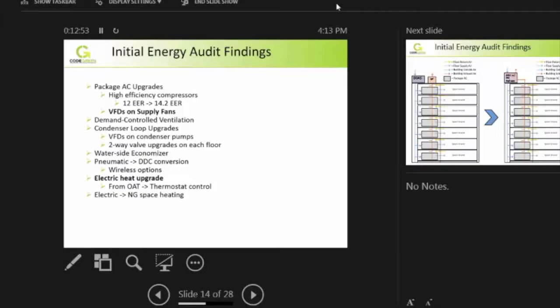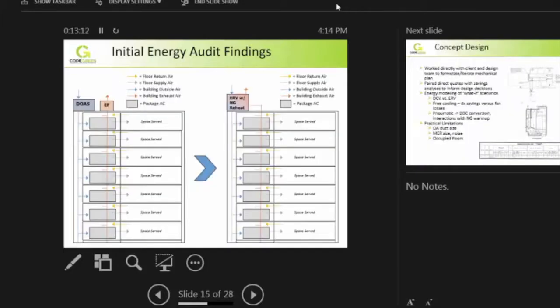Water-side economizer had actually been taken out of a lot of the existing package AC units in the building, so there was an aversion by the O&M staff to using them. But we wanted to evaluate if it made sense at this building. Unfortunately, the plenum for the outside air system wasn't big enough to do air-side economizing, which is the clear first direction you'd want to go with that type of system.